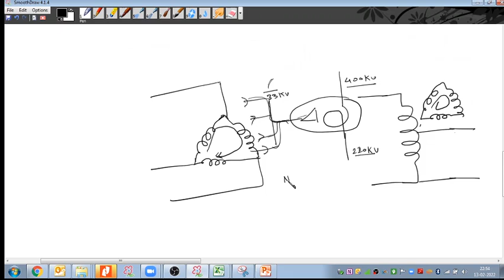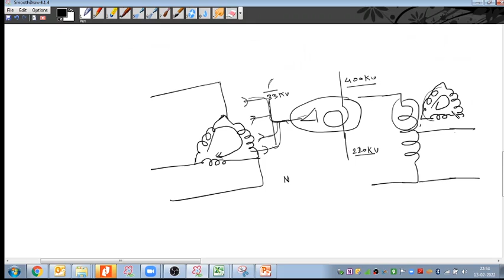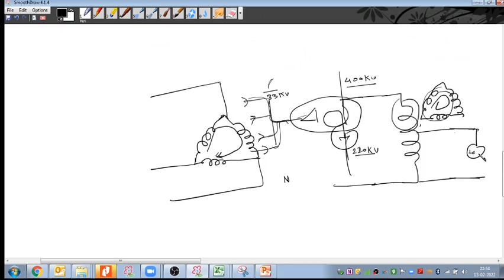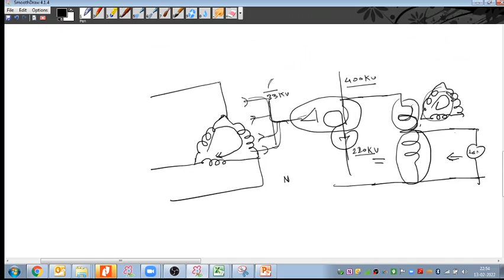And what about the power balancing? Actually, we know the formula N1 V1, the flux. This side we have the source, suppose, and this side we have the load. So this side flux is balanced with here, right? But if I do not put the delta here, this side flux is not balanced because there is no opposite flux. So to balance this portion of the winding, the manufacturer inherently has to provide this winding, and if we put some load here, this portion of the winding is balanced with this load. This is called power balance or flux balance.